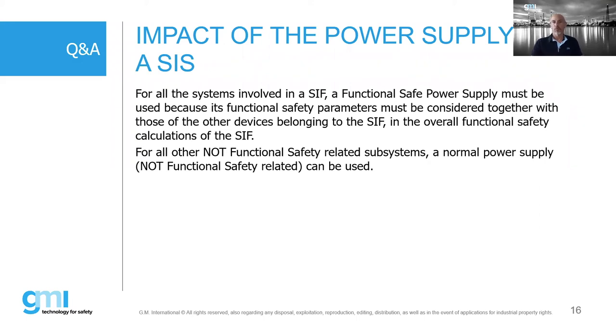Yes, for all the systems involving a SIF, a functional safe power supply must be used, because its functional safety parameters must be considered together with those of the other devices. We can say in the presentation that it is important to use a separate power supply because it is certified and has the calculation. I've made a calculation with respect to the standard power supply. For this, it is important to use a SIL power supply system.